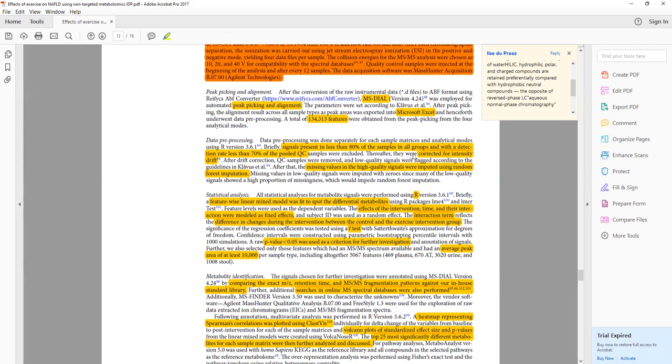After that, they would correct for the intensity drift. We refer to that as a batch effect. So there's a sort of batch effect if you do your samples in batches. That can be due to temperature, humidity in the lab, your instrument tuning being slightly different, you made up a new internal standard, whatever. There can be a lot of reasons why you use your QCs then to correct for a batch effect.